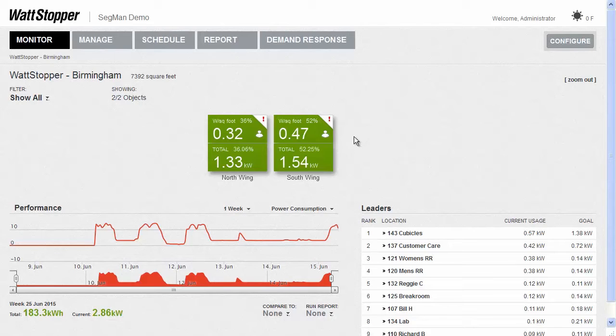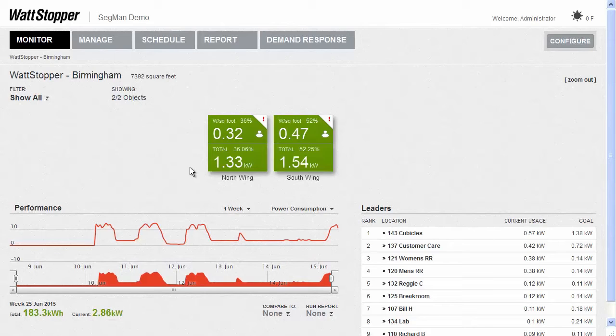For this single-story site, notice that it's been set up to display two tiles, one for each wing. This building has enhanced room controllers — the larger format units for dimming, or available for plug load as well. They have internal current transducers, so once we assign voltages to each room controller, we can read the power usage for each controller, and therefore each room.